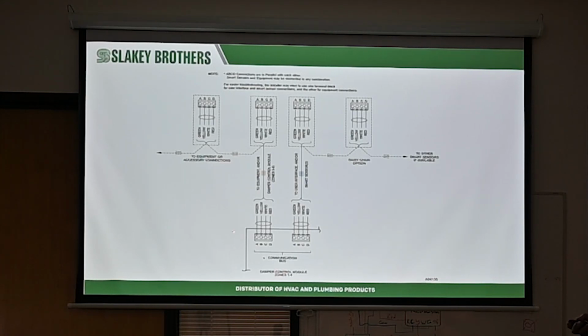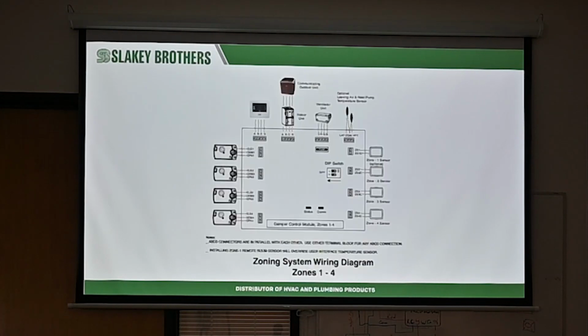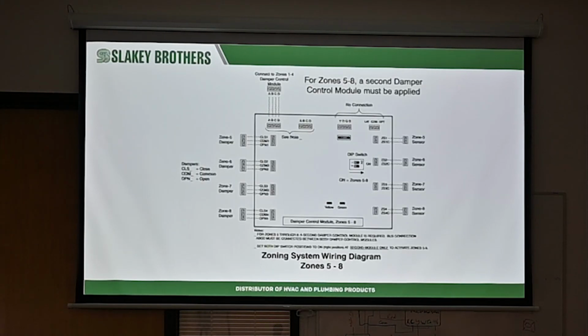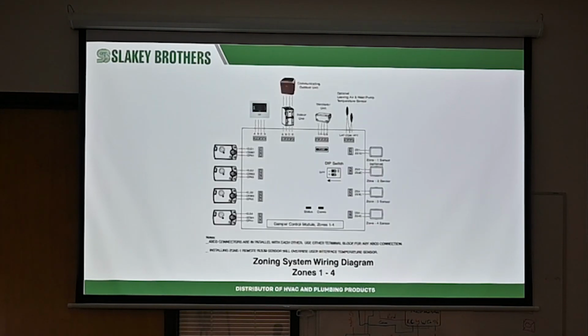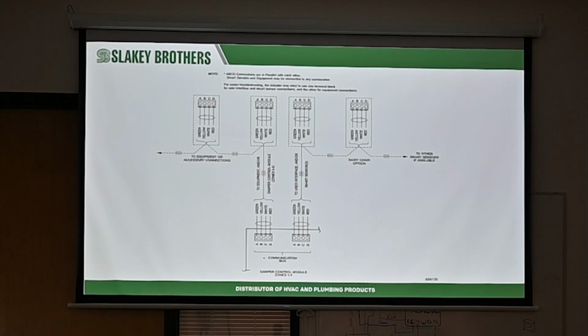But what they want is to reserve one of the ABCDs for the equipment. So you can see ABCD to the furnace to the outdoor unit. And then the other ABCD will go to the main Connex first. And then from there you start adding all your zones. And again, this could be as many as 8. But as you can see, if you do 8 zones, you at least have one other ABCD that you can run communication from as well. So this is how you do the additional zone 5 to zone 8. Anyway, in the perfect world, they want to go from the main Connex to a zone sensor, smart sensor, to the next smart sensor, to the next smart sensor.